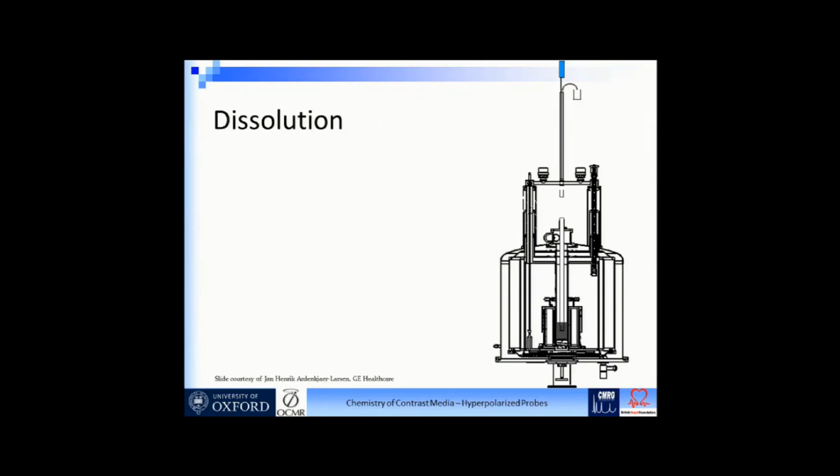So you've got your sample immersed in liquid helium, so it's down at very low temperatures at 1 Kelvin. It's in the bottom of a high field, sort of 3.5 Tesla MR system, and it's been polarizing for about 45 minutes. So that's definitely one of the disadvantages of this technique over parahydrogen, is that the duration of time taken to enhance the polarization is much longer.